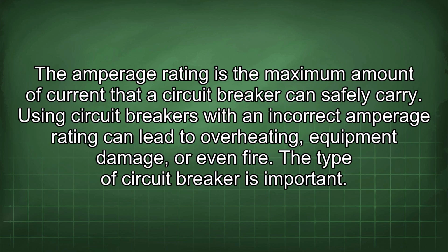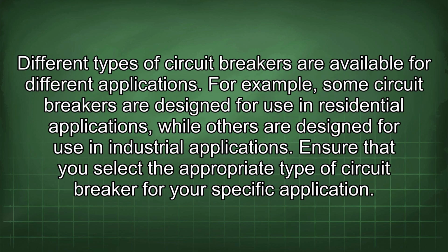The amperage rating is the maximum amount of current that a circuit breaker can safely carry. Using circuit breakers with an incorrect amperage rating can lead to overheating, equipment damage, or even fire. The type of circuit breaker is important. Different types of circuit breakers are available for different applications. For example, some circuit breakers are designed for use in residential applications, while others are designed for use in industrial applications. Ensure that you select the appropriate type of circuit breaker for your specific application.